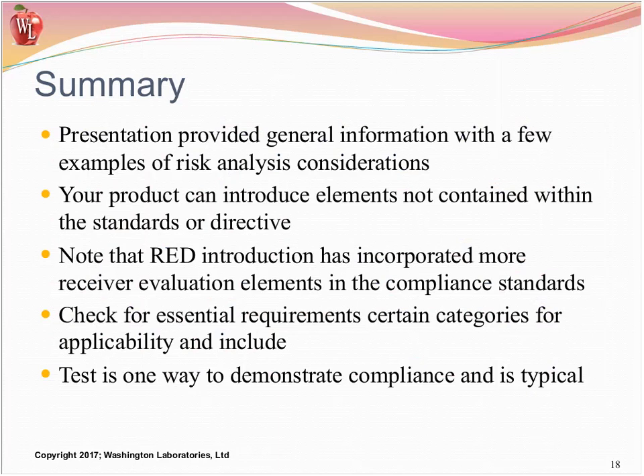There's lots of definitions there. I feel that this is appropriate for what we're working with. It allows some flexibility in how we cope with it, and your notified bodies are going to ask you to be clear about it. They're going to drive what they're asking for because they're going to look at it very thoroughly. I know that some of the bodies look at this, make sure the laboratory did an extreme temperature thing, that they covered the range for all of the various tests where that is required.